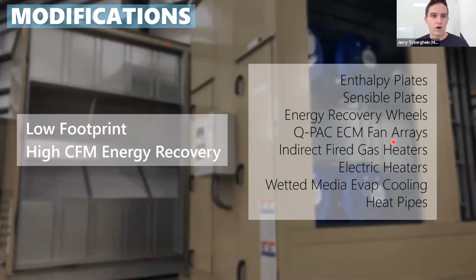In general, our modifications are trying to always save footprint and trying to increase your capabilities with what you can do with the more complex units like energy recovery type units. So low footprint, high CFM energy recovery. We do that by using the components on the right. So different types of plate heat exchangers, wheels, different types of fan arrays, heaters, wetted evap cooling, and heat pipes. So I'm going to go over a couple different examples of these types of components and show you some cool pictures and CAD drawings.